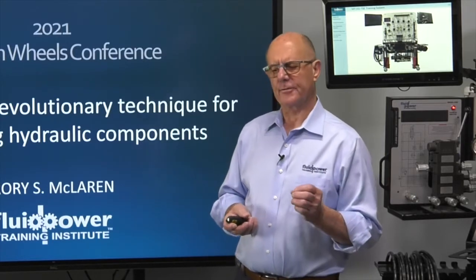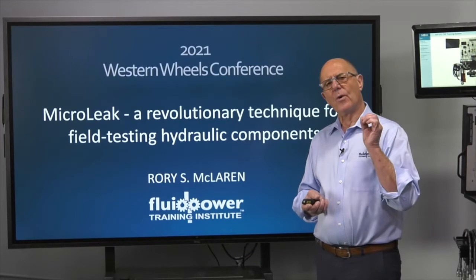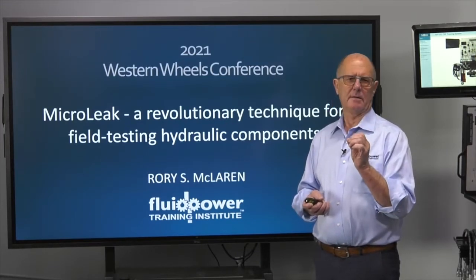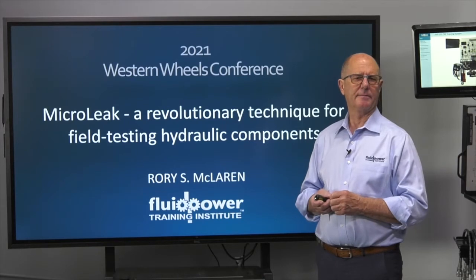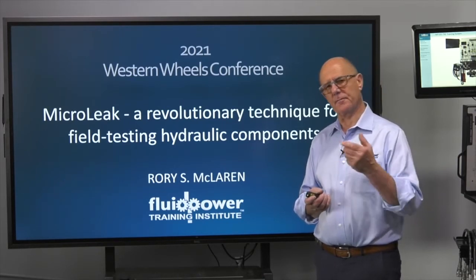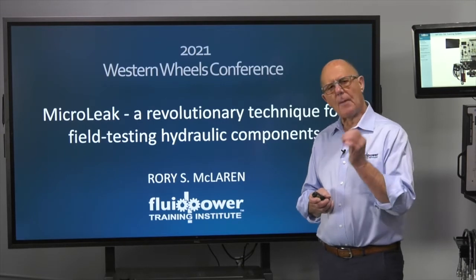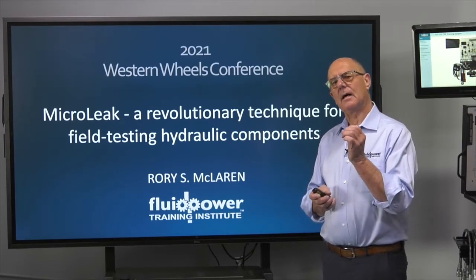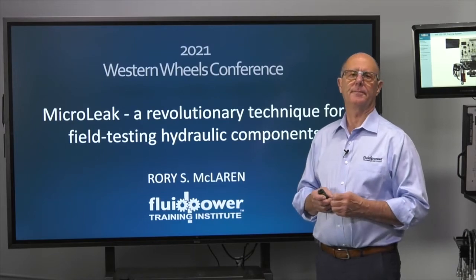The other problem is that, and we need to understand this clearly, whenever there is a speed problem on a hydraulic actuator—actuator is the collective term for cylinders and motors—when an operator complains that the hydraulic cylinder or motor is slowing down, understand this: it can only be a flow-related problem. It cannot be a pressure deficit. It's impossible. In other words, you will not find the problem with a pressure gauge.